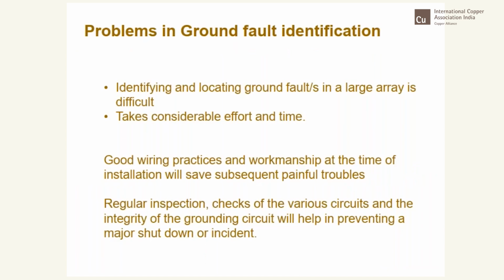So what is the problem in ground fault? Identifying and locating ground faults in a large array is extremely difficult. If it is a small rooftop system, 5 kilowatt, 10 kilowatt on the roof, it is fine. But if you are going to have a megawatt size system, this is going to be difficult. Good wiring practices, that's what I was insisting: at the time of installation itself, you have to exercise great care, and then follow the right practices and the right conventions recommended by codes and standards. And despite all these things, we still have to regularly inspect, otherwise there could be infestations of pests and things like that. It is unavoidable. So it is very important how frequently we inspect, check, and then take adequate precautions.